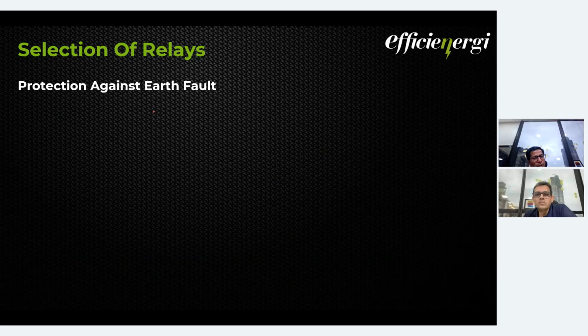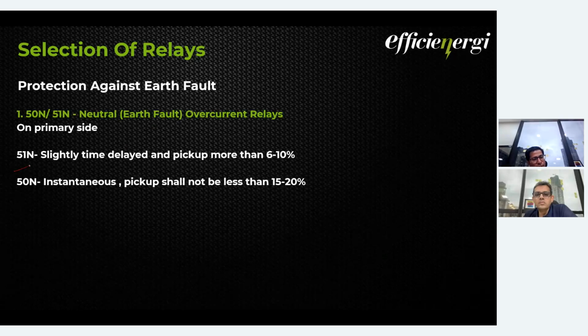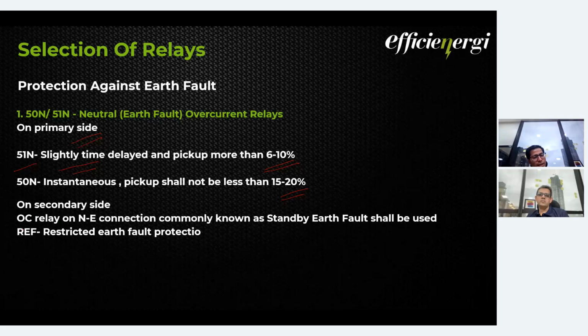Protection against earth fault for a transformer, again it is the same. So 51N is slightly time delayed and pickup more than 6 to 10% on the primary side. Our instantaneous pickup shall not be less than 15 to 20%. This we will be covering in our next webinar, where we will talk in much more detail about the protections. On the secondary side, an overcurrent relay on the neutral earth connection, commonly known as standby earth fault protection, we can give directly. Then we can also give on the secondary side a differential protection, that is restricted earth fault protection.